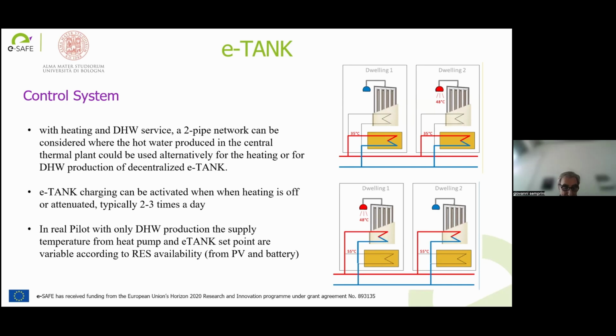For the general solution with both heating and domestic hot water service, a two-pipe network can be considered where the hot water produced in the central thermal plant could be used alternatively for heating and also for domestic hot water production in a tank.